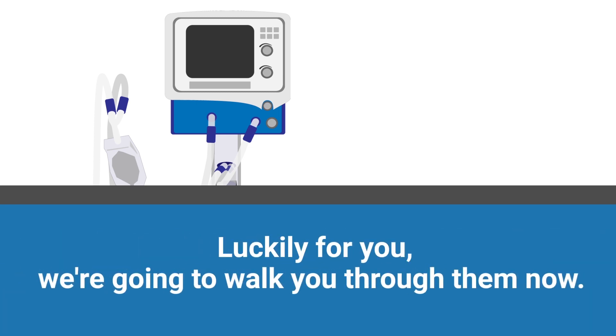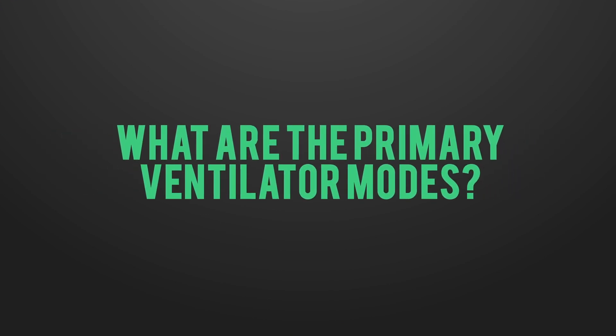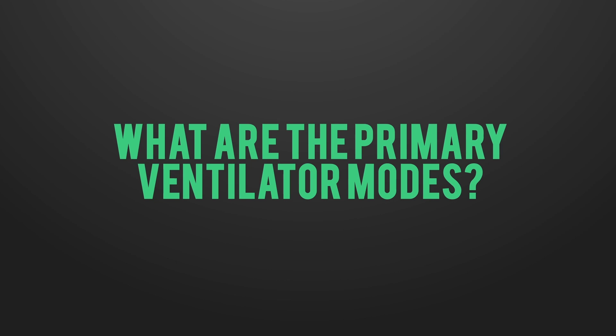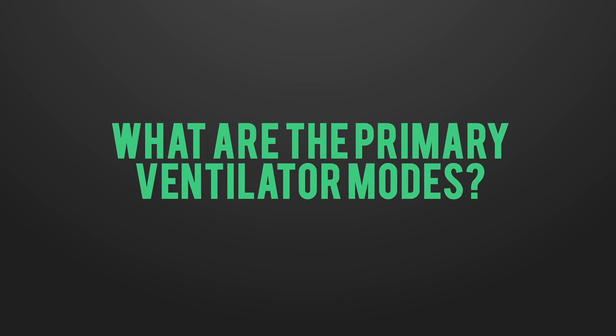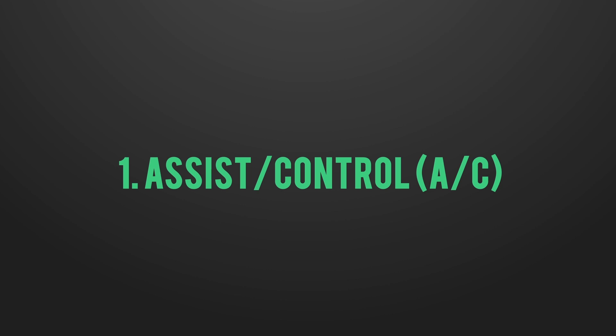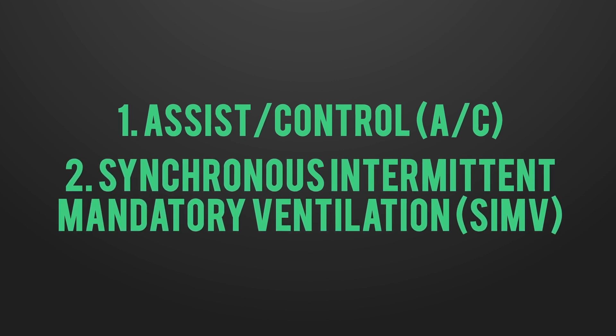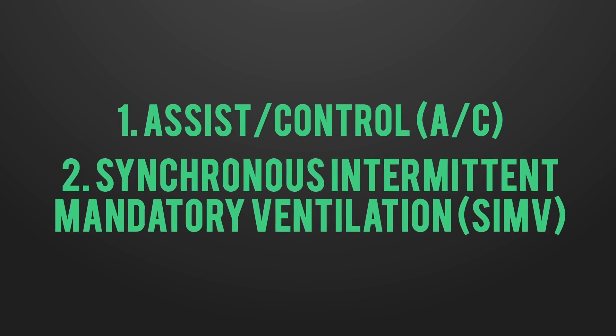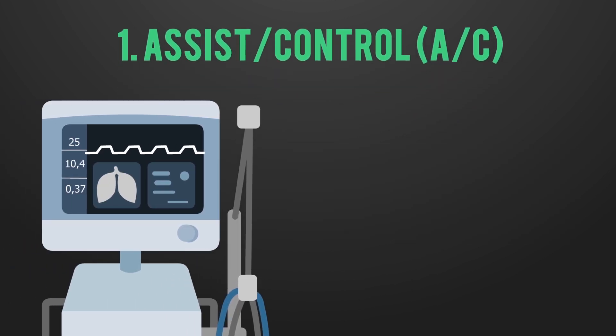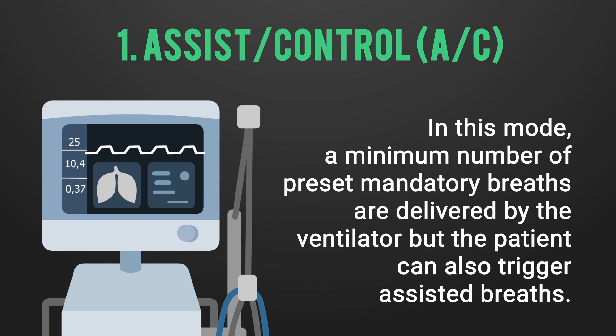The two primary ventilator modes — the operational modes of the machine — are Assist Control (AC) and SIMV, which stands for Synchronous Intermittent Mandatory Ventilation. In Assist Control mode, a minimum number of preset mandatory breaths are delivered by the ventilator, but the patient can also trigger assisted breaths.